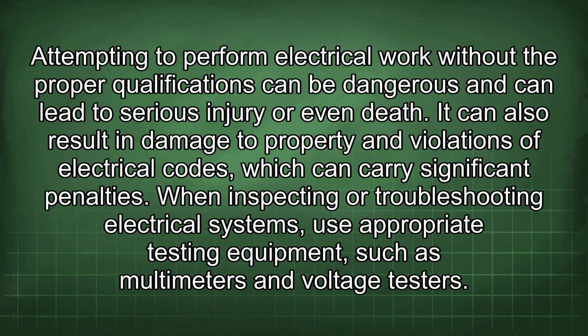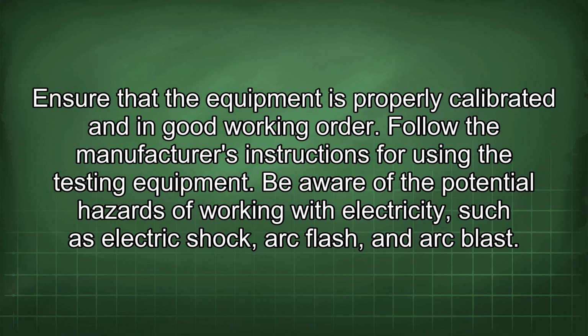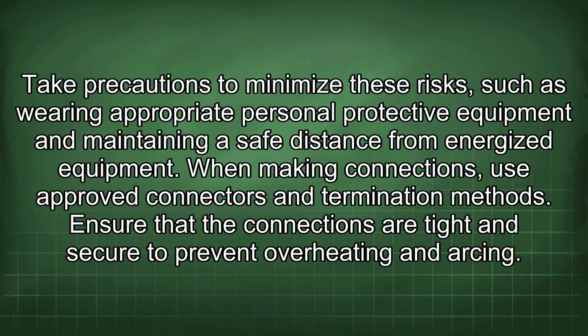When inspecting or troubleshooting electrical systems, use appropriate testing equipment such as multimeters and voltage testers. Ensure that the equipment is properly calibrated and in good working order. Follow the manufacturer's instructions for using the testing equipment. Be aware of the potential hazards of working with electricity such as electric shock, arc flash, and arc blast.